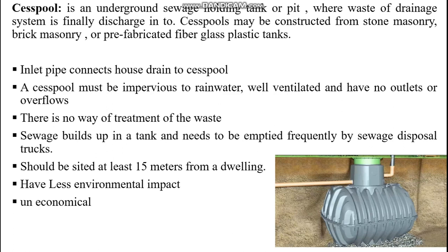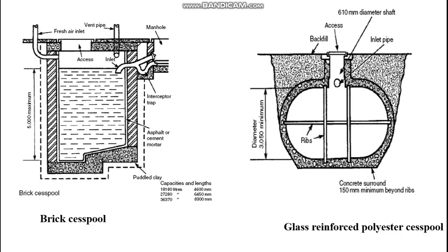A cesspool must be impervious to rainwater, well ventilated, and have no outlets or overflows. There is no treatment of waste — sewage builds up in the tank and needs to be emptied frequently by sewage disposal trucks. It should be sited at least 15 meters from a dwelling. Cesspools have less environmental impact and are uneconomical. Types include glass-reinforced polyester cesspools and brick cesspools.